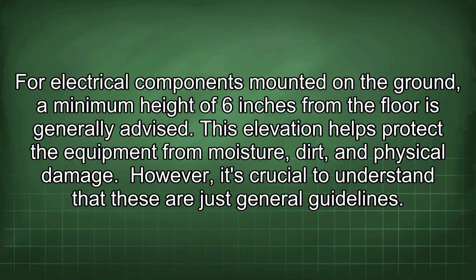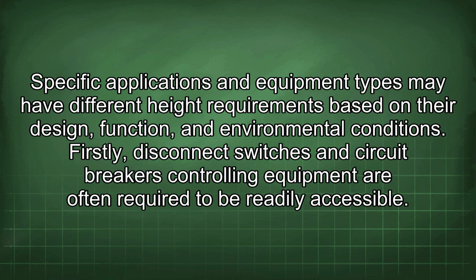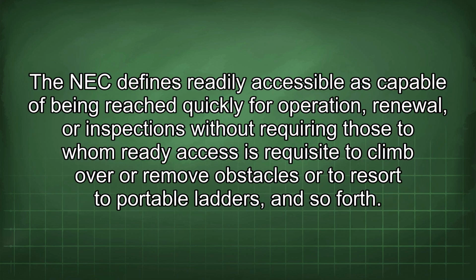However, it's crucial to understand that these are just general guidelines. Specific applications and equipment types may have different height requirements based on their design, function, and environmental conditions. Firstly, disconnect switches and circuit breakers controlling equipment are often required to be readily accessible. The NEC defines readily accessible as capable of being reached quickly for operation, renewal, or inspections without requiring those to whom ready access is requisite to climb over or remove obstacles or to resort to portable ladders, and so forth.